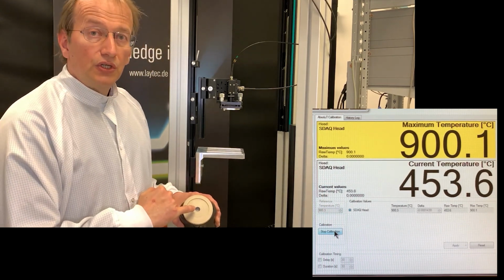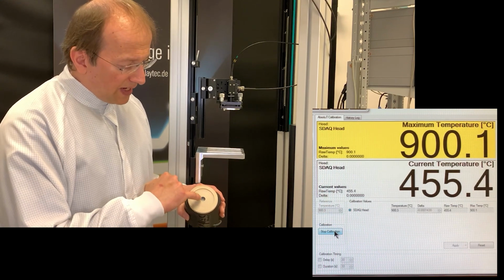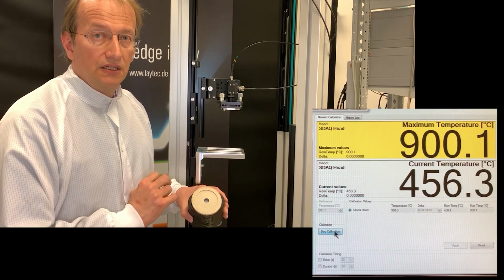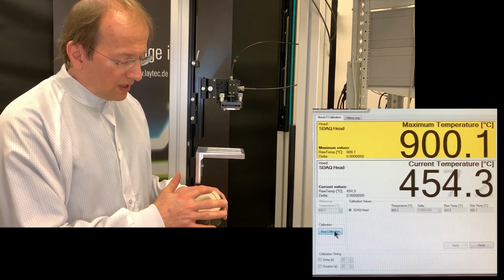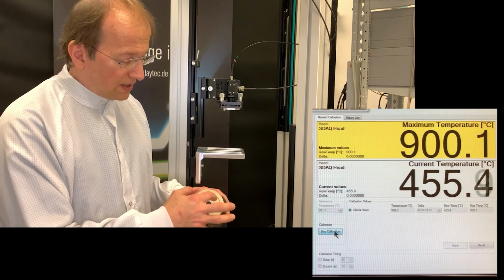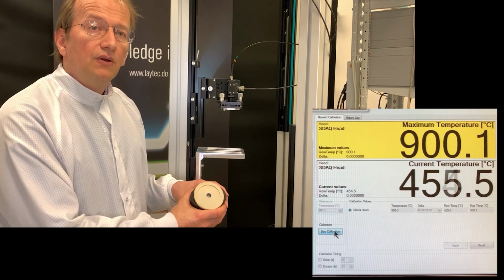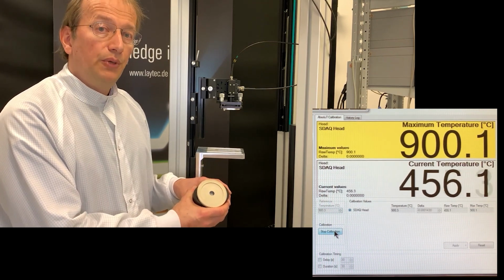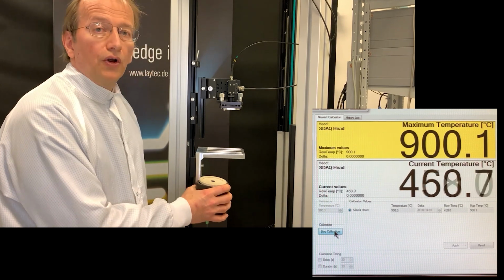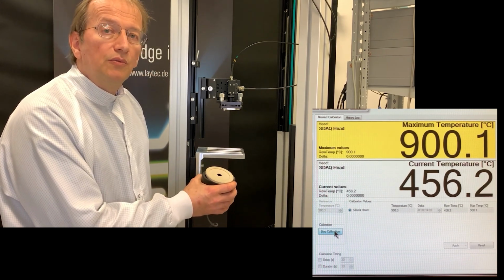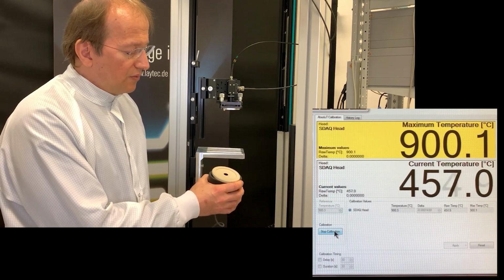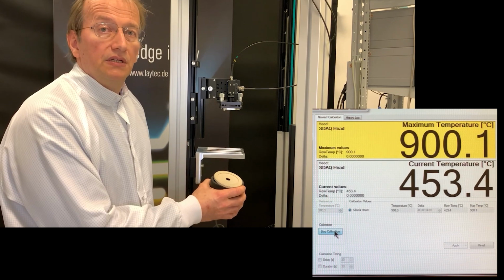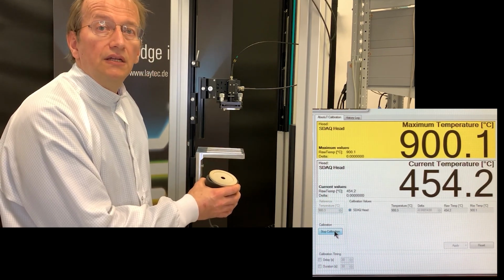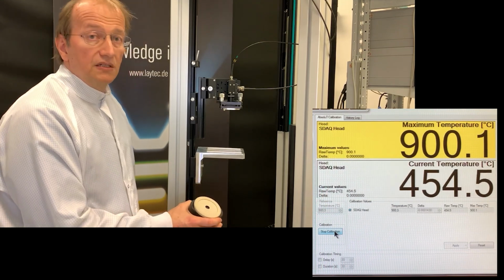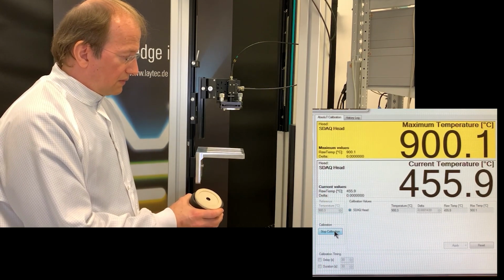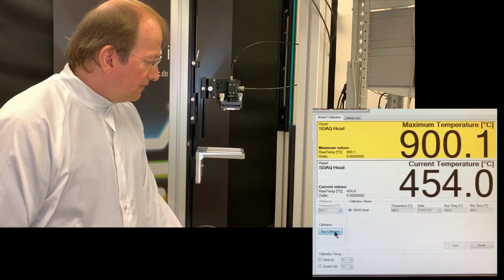So the only target with our manual movement is to find this relative maximum. So we have this tiny light spot of the EpiTT, which is about 2 millimeters in diameter, and that needs to match somewhere within this big exit slit. So the radiation, the emission is constant, is homogeneous across this diameter. That's why we have a certain degree of freedom where we find the maximum. So the maximum is not like a peak, but it's more a plateau. That's why you look for a value which appears to maximum. And then you move a little bit up and down, back and forth, to kind of map this diameter, and the reading should react accordingly. And once we found the maximum, which is in our case performed, then basically we are done.